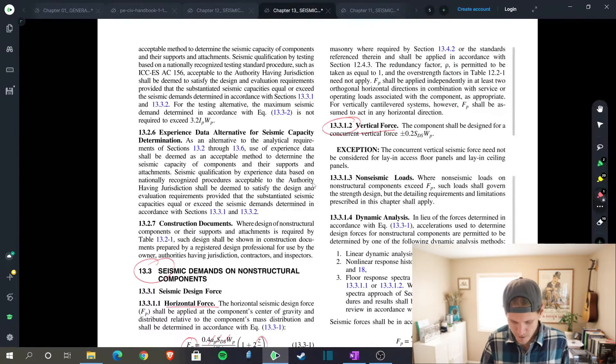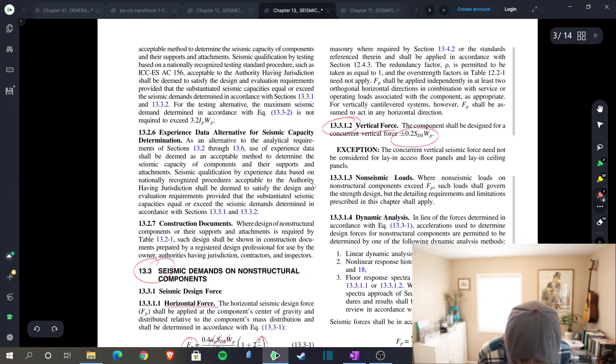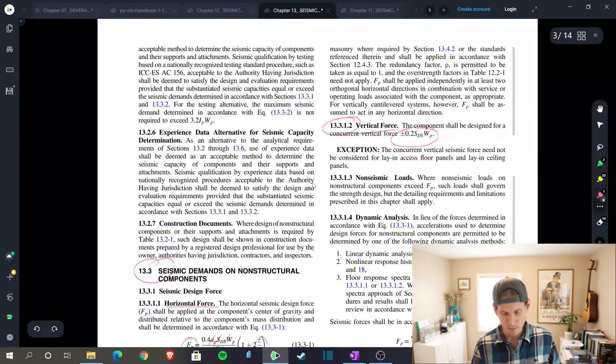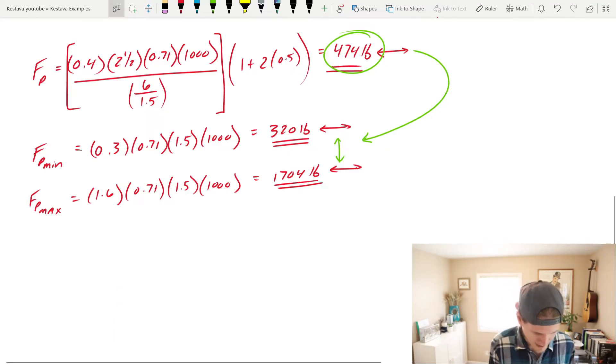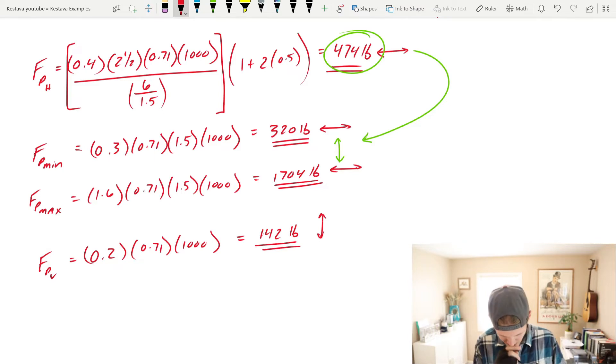And simply, for vertical force, the component shall be designed for a concurrent vertical force of plus or minus 0.2 SDS weight of your unit. Let's go plug that in. Since we're back here, I'm actually going to slap on a little H to our FP force. That's horizontal. And then we're finding FP vertical, just to keep everybody super clear here. That equals 142 pounds. And that's in the vertical direction, up and down.